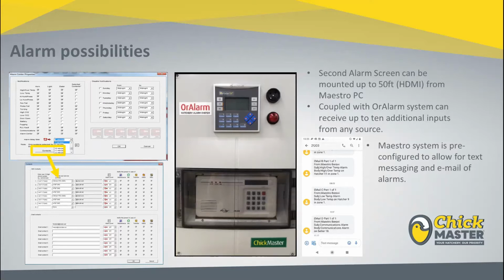For example, relying on email and text messaging is fairly reliable, but a telephone call to back up the alarm makes a lot of sense. And you can configure on these screens how you'll be notified. You can configure them to just sound the horn of the OrAlarm, show the light, activate the dialer. So, in your most critical alarm situations, you probably want to activate the dialer. And the selected contacts means it will email or text message for these alarms if you check selected contact.